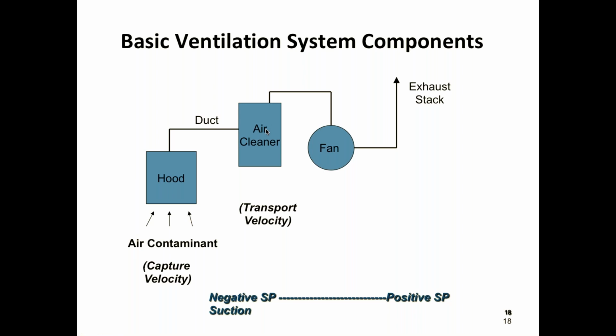If it's particulates like grinding material, then it's probably going to be a media filter. If it's VOCs, it may be an activated charcoal filter. But you want some way to scrub it out of the air. Then the fan. Notice the air cleaner is in front of the fan. Why not? You might as well protect the fan too, right? And then an exhaust stack to get the air you're moving completely out of the building. So this hood and all of this stuff is connected with some transport mechanism, ductwork, right? So you need to understand how this air is moving through this ductwork so that you can actually design this system.